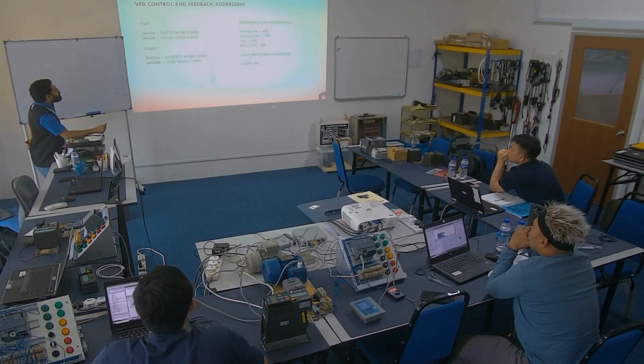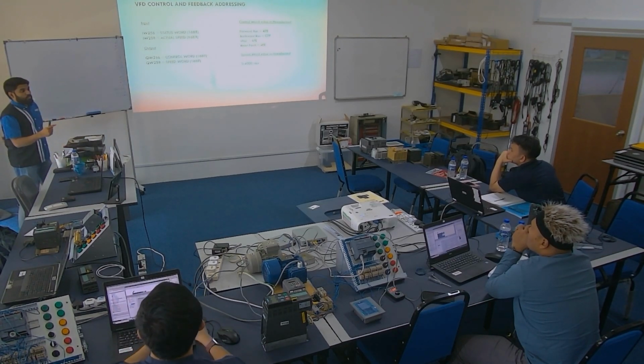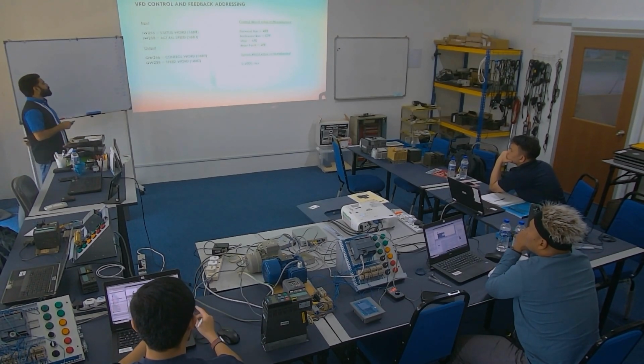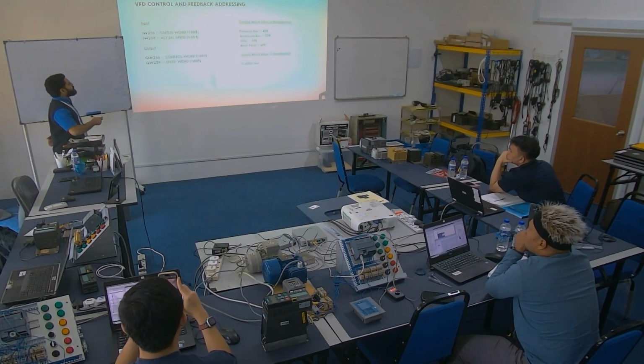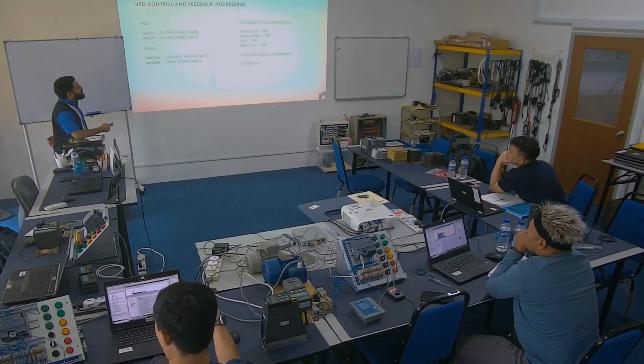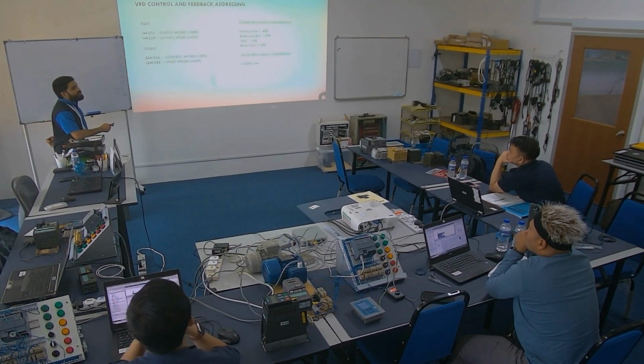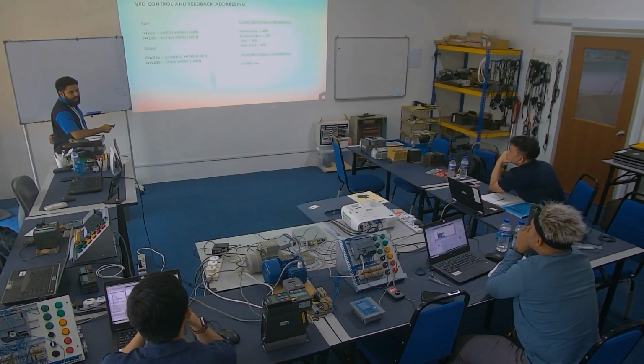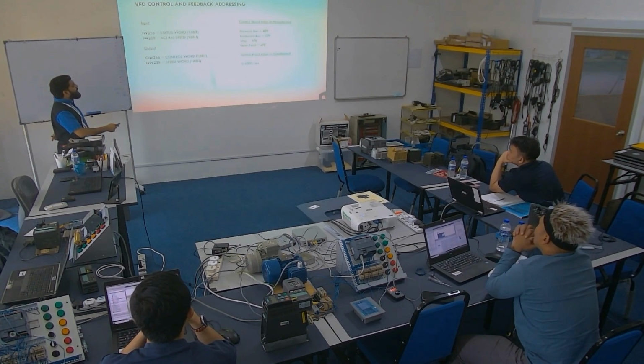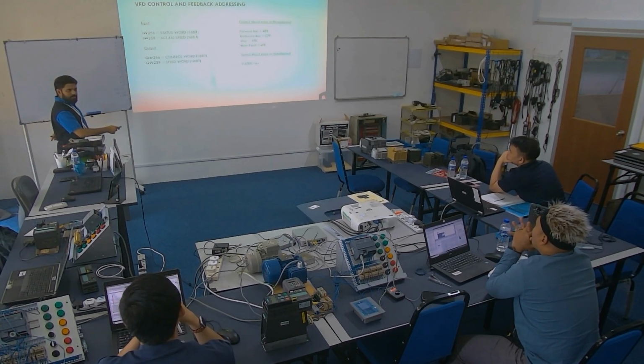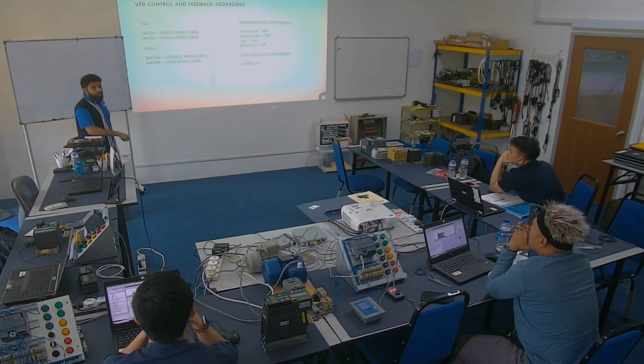Then output, output is the control bit, the first one. Control is you control the motor, then speed word. So you see, control word is 16-bit, and the control word value is actually in hexadecimal. So this is where we commonly use hexadecimal. I got this data from the Sinamics manual.